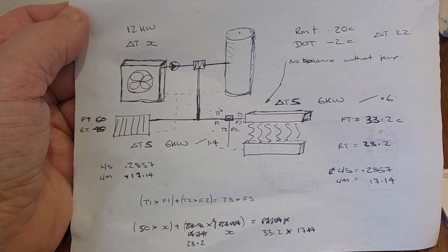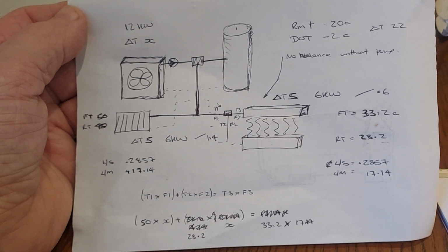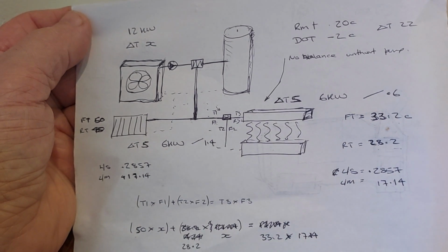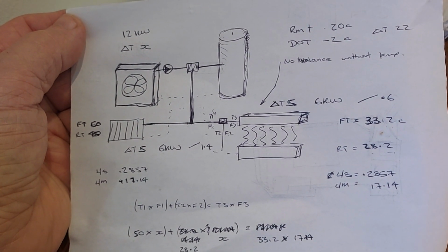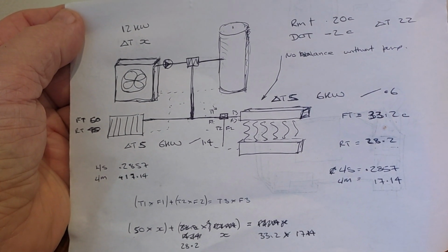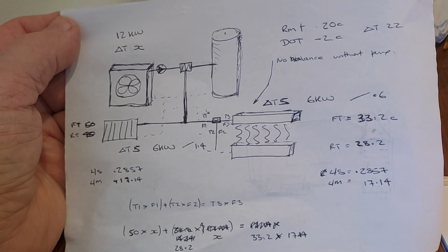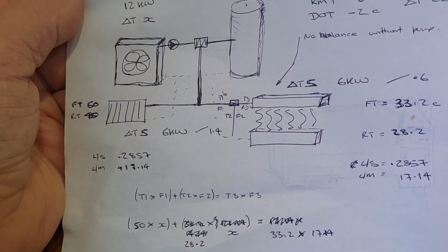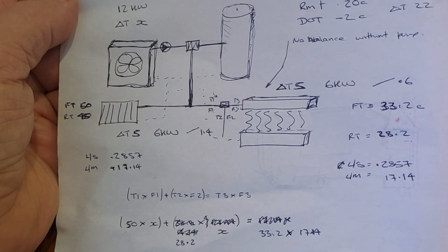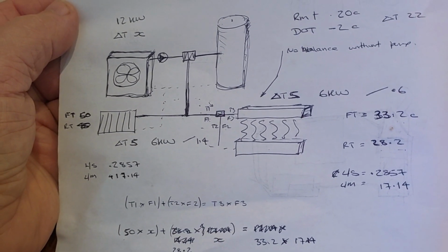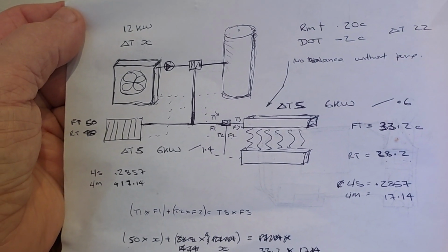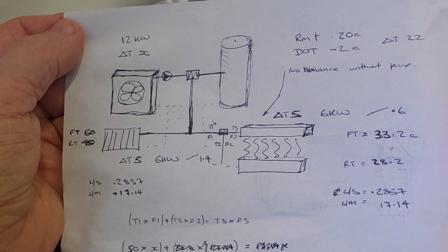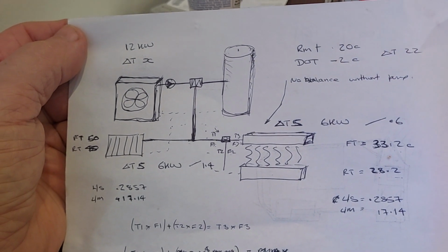The other thing I would argue is that if we use a low loss header to get the heat pump and the system in balance, our overall return temperature should be lower, and therefore delta T5 at the heat pump should be able to give us a lower output. So the output temperature of the heat pump would always be correct for the radiators, the flow would be correct, so there'd be no loss of efficiency from our heat pump if we were to use hydraulic separation.